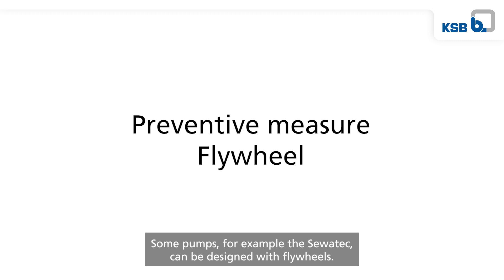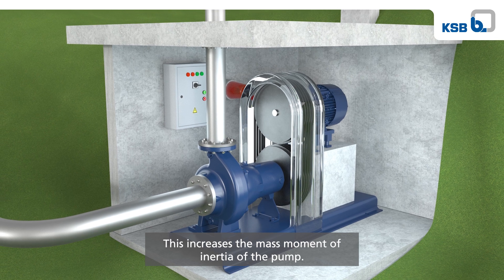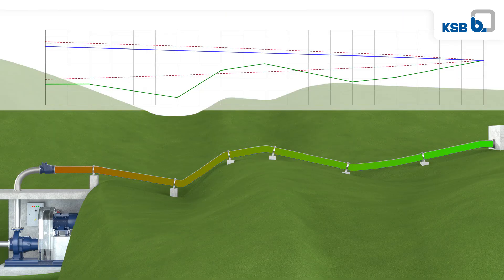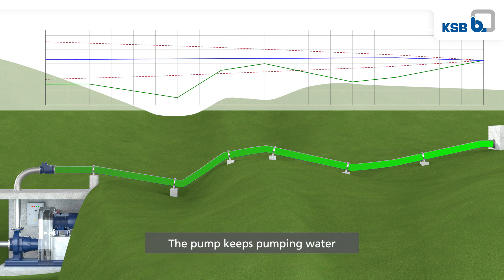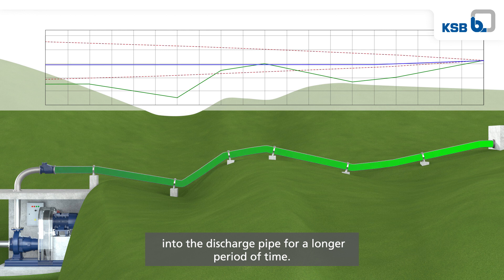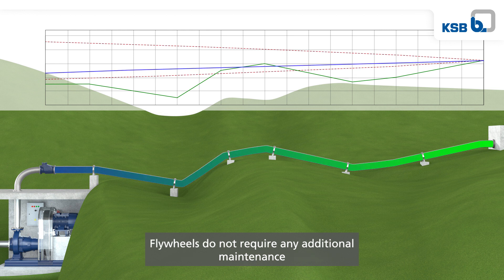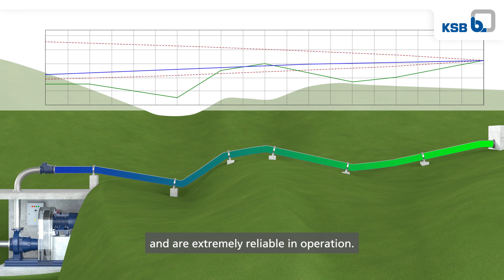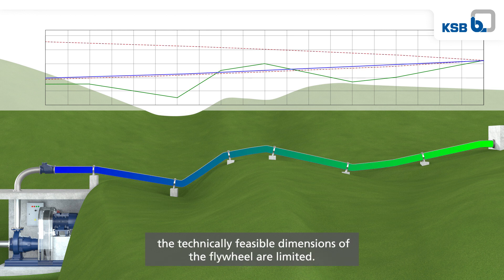Some pumps, for example the Sewatec, can be designed with flywheels. This increases the mass moment of inertia of the pump. If the pump fails, the pump speed drops slower, and the pump keeps pumping water into the discharge pipe for a longer period of time. As a result, the first negative pressure wave can be significantly reduced. Flywheels do not require any additional maintenance and are extremely reliable in operation. However, the longer the pipeline, the larger the flywheel would have to be, and in the case of very long pipelines, the technically feasible dimensions of the flywheel are limited.